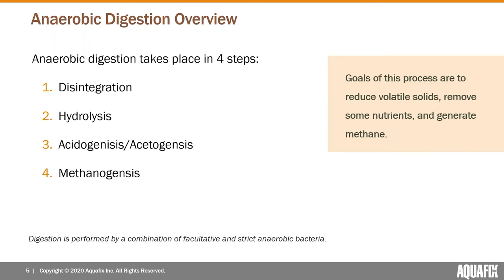The anaerobic digester process is a four-step process — sometimes called five steps if you break step three into acetogenesis and syntrophic acetogenesis, which sound similar but are slightly different. Starting with the most important step: disintegration, where you're breaking down large chunks of solids into small fine particles to give bacteria enough surface area to excrete exoenzymes, which hydrolyze particles into soluble compounds like fatty acids and smaller amino acids.